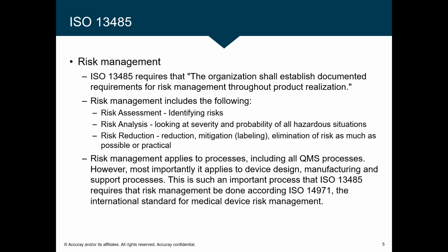the product labeling. This is something that is very difficult in some cases to capture everything during the development, especially on new products that aren't released yet, because sometimes you don't know the level of risk you're going to be assuming with a particular product. So this is another reason why our labeling is always in a constant state of update, because additional risks are identified and you have to mitigate that within your labeling.